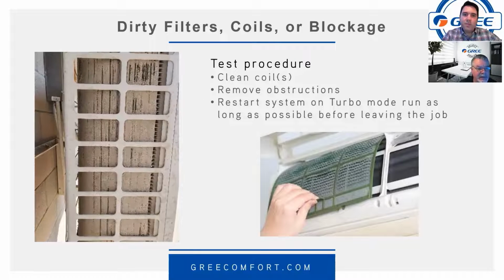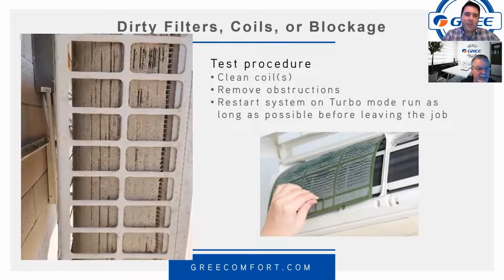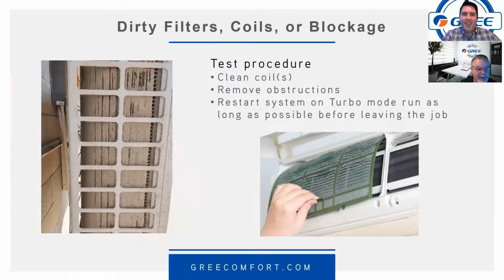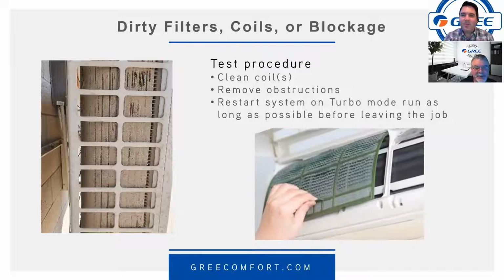Take a look at this condenser coil. Oh, that's rough. That's pretty dirty. Do you think that might cause an E1 error? That could cause an E1, Keith. I would bet that would cause an E1 error pretty quick, certainly in cooling mode, right?